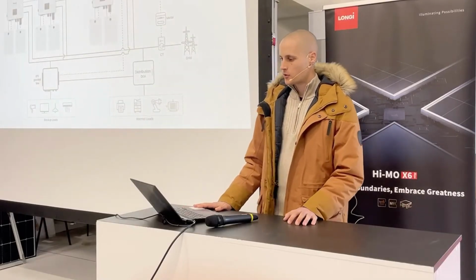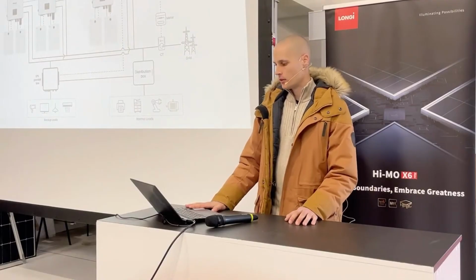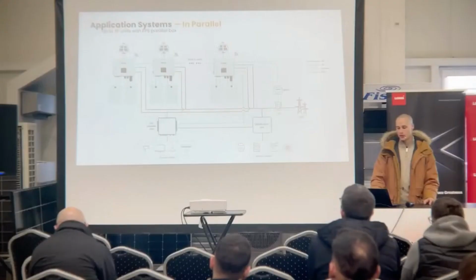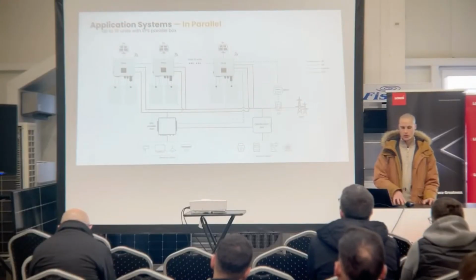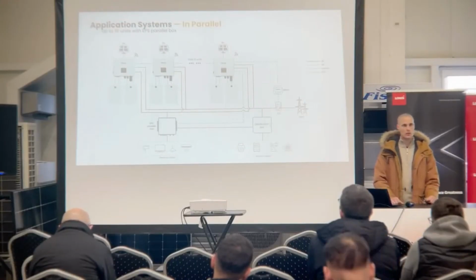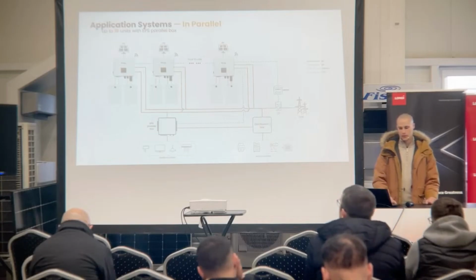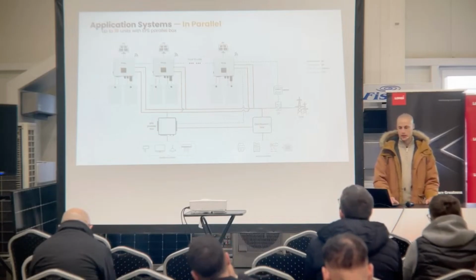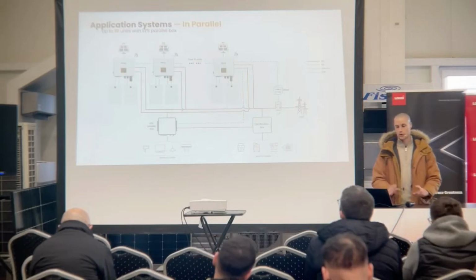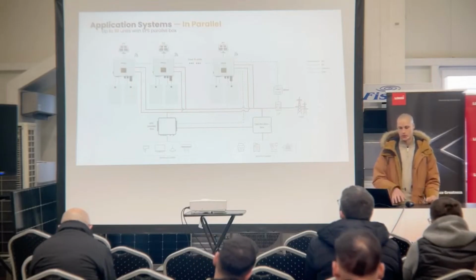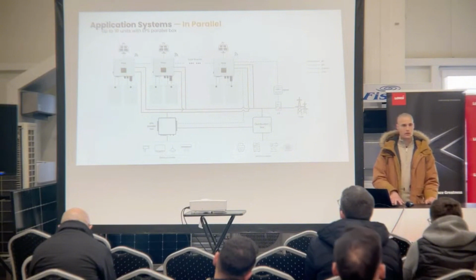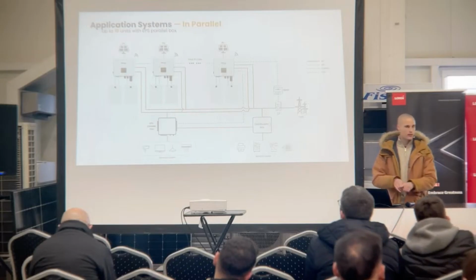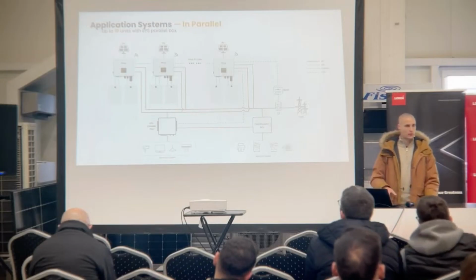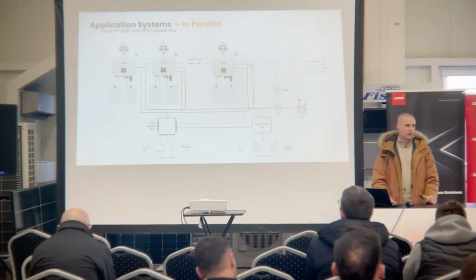Some application system scenarios are the same with the batteries. So basically, with the Pro version, you can connect up to 10 pieces in parallel altogether. They have to have the batteries on each of them if you would like to connect them in parallel for off-grid mode. And until 3 pieces in parallel connection, you don't need any extra device, so you can just connect the grid side and the EPS side. But if you're using more than 3 pieces of inverters, you have to use the EPS parallel box.